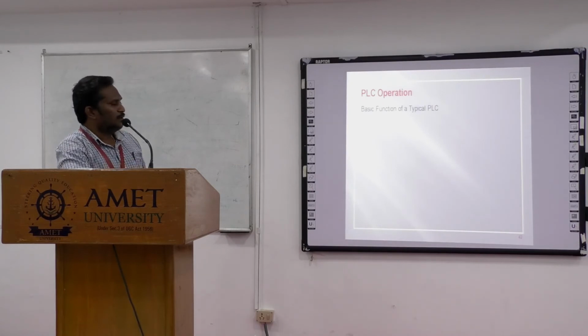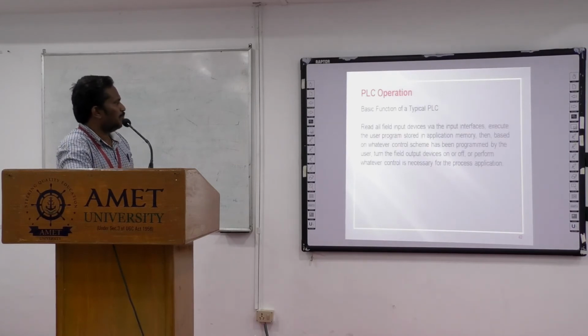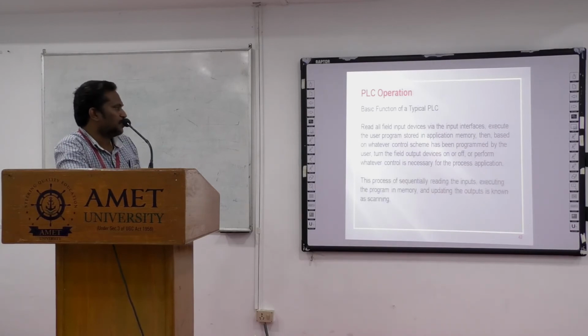PLC operation. The basic functions of a typical PLC are: read all field input devices via the input interfaces, execute the user program stored in application memory, then, based on whatever control scheme has been programmed by the user, turn the field output devices on or off or perform whatever control is necessary for the process application. This process of sequentially reading the inputs, executing the program in memory and updating the outputs is known as scanning. So we are going to see the scanning cycles one by one.